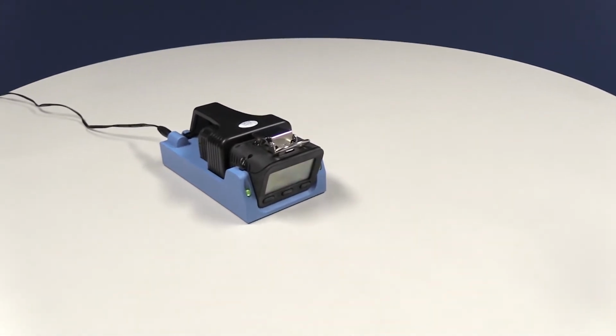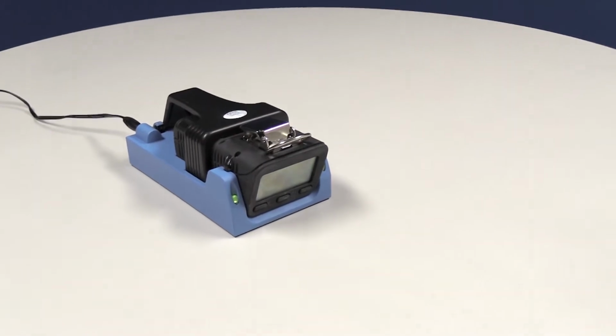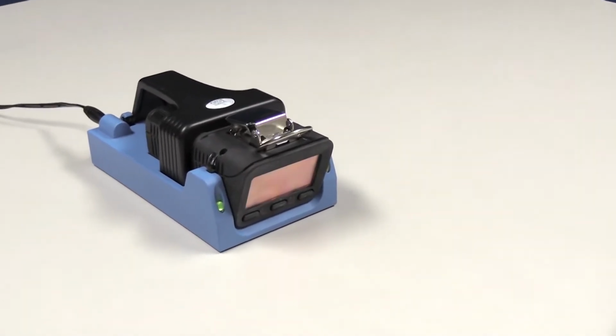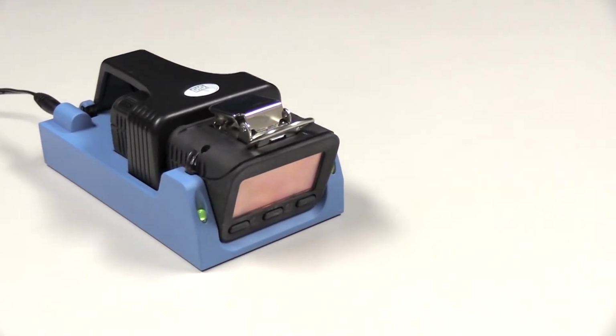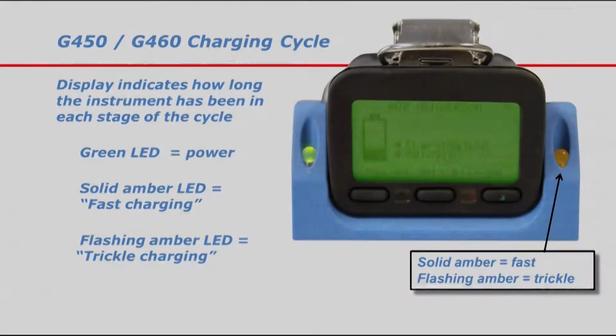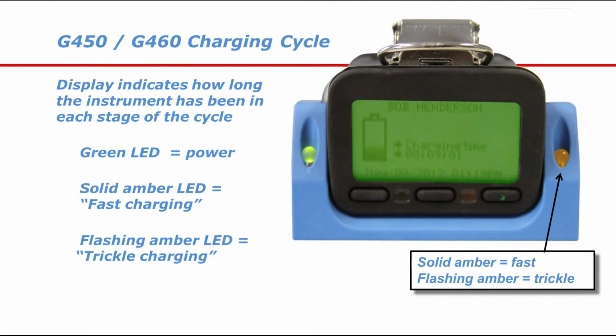The green LED indicates that the charging cradle has power. Once you insert the instrument into the charger, the G450 display will show you the charging status. During the fast charging phase of the charging cycle, the amber LED is continuously lit. When the battery pack is completely depleted, it can take up to 6 hours to complete the fast charging cycle. When the battery pack has been charged to 90%, fast charging is complete, and the amber LED will begin to blink.